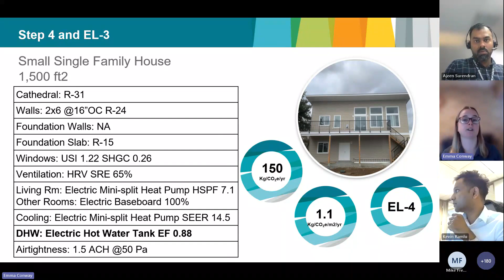Since the space heating load for this home was so small, approximately 15,000 BTUs, did it make sense to have a forced air heat pump or forced air furnace? No, it did not. With such a small heating load, it made a lot more sense, even space-wise, to just go electric, primarily electric baseboard for this example.